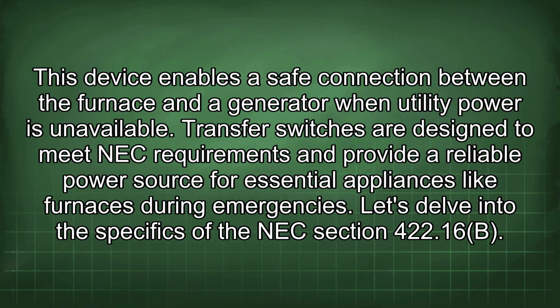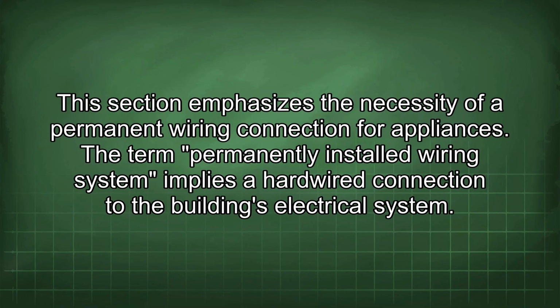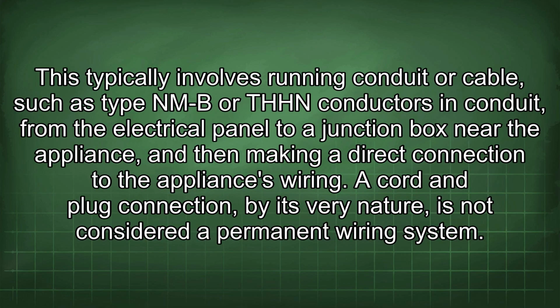Let's delve into the specifics of the NEC Section 422.16b. This section emphasizes the necessity of a permanent wiring connection for appliances. The term permanently installed wiring system implies a hardwired connection to the building's electrical system. This typically involves running conduit or cable, such as type NMB or THHN conductors in conduit, from the electrical panel to a junction box near the appliance, and then making a direct connection to the appliance's wiring.